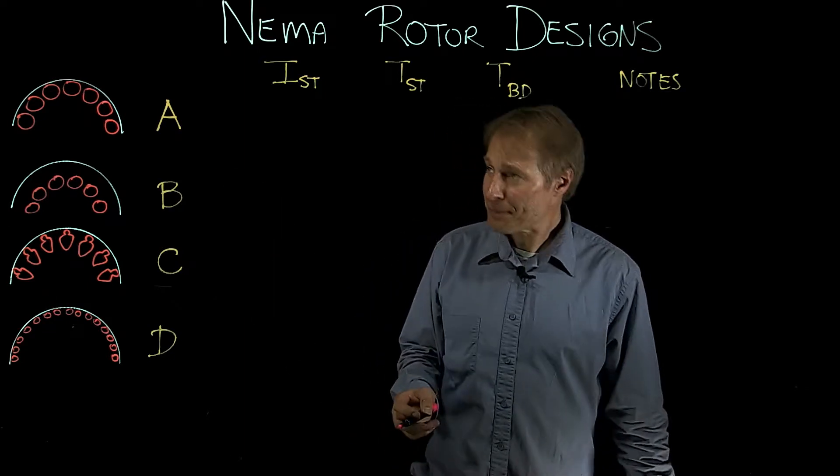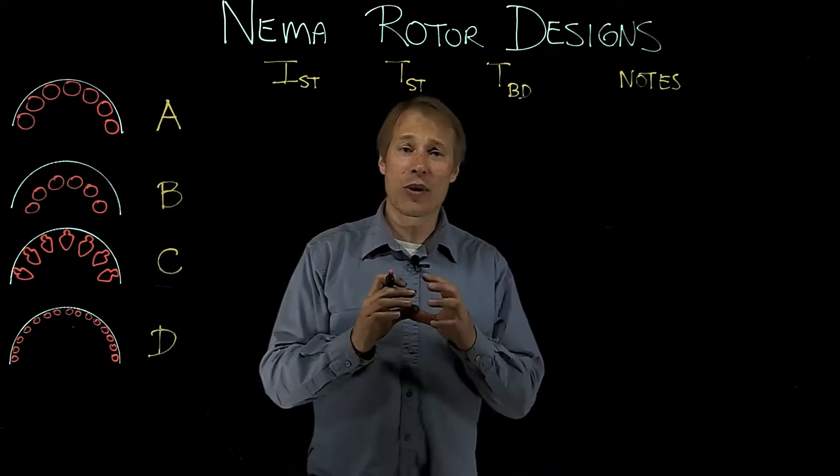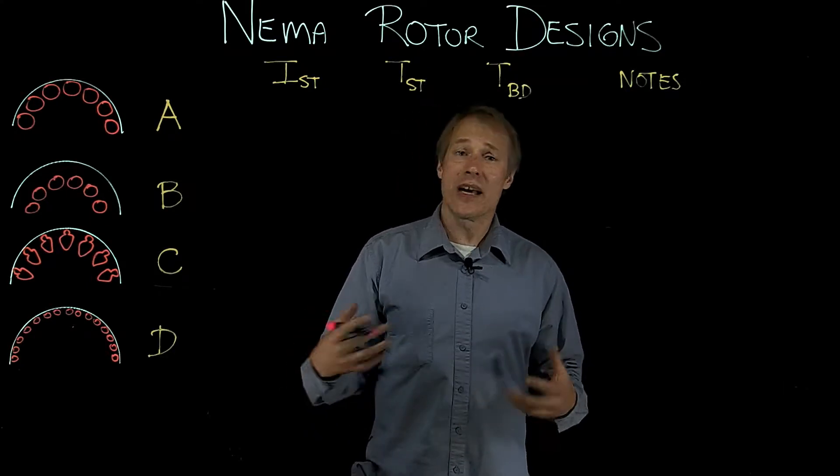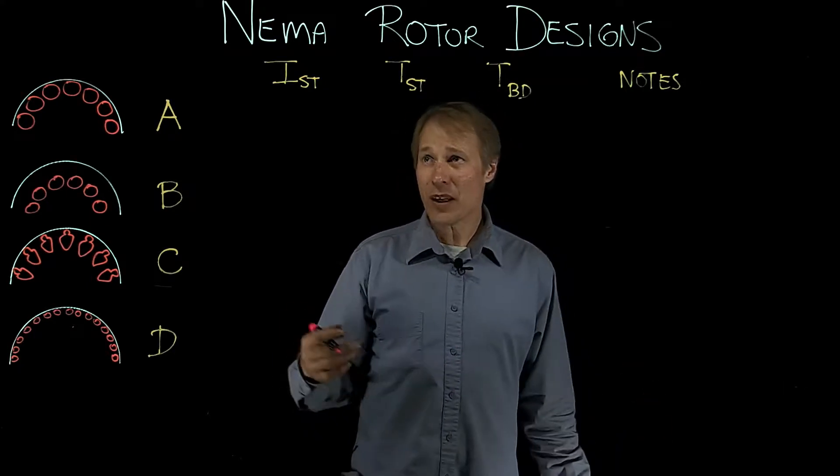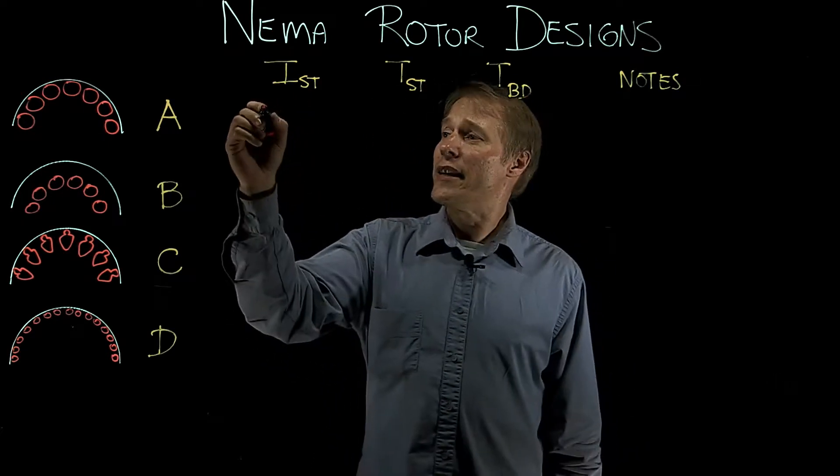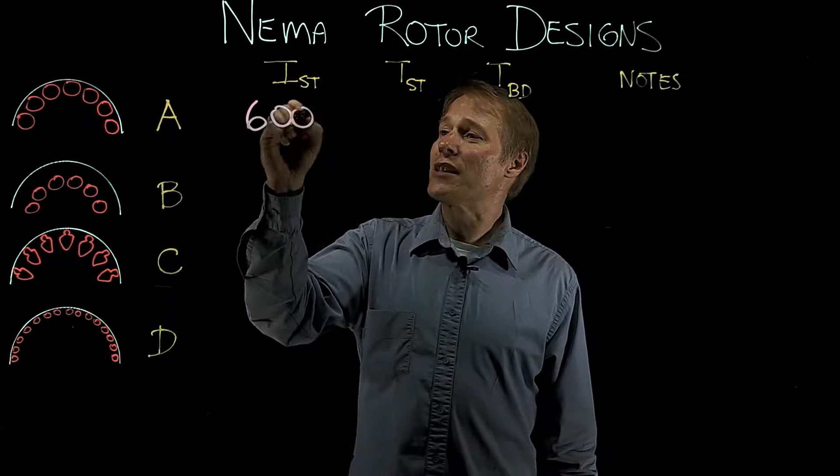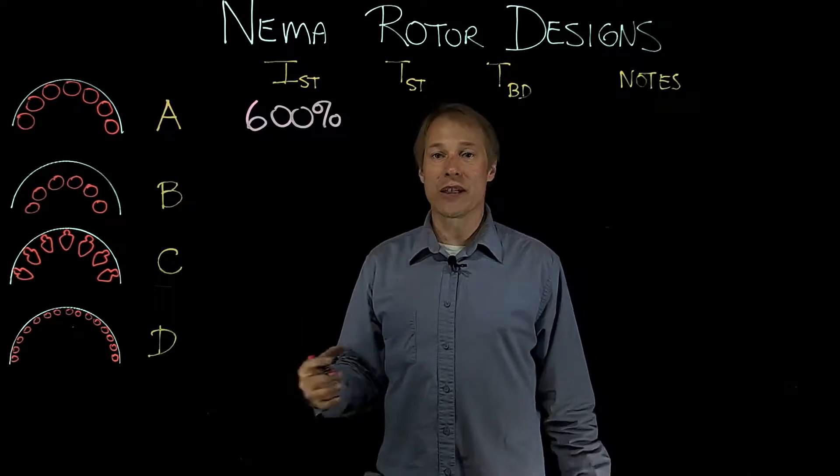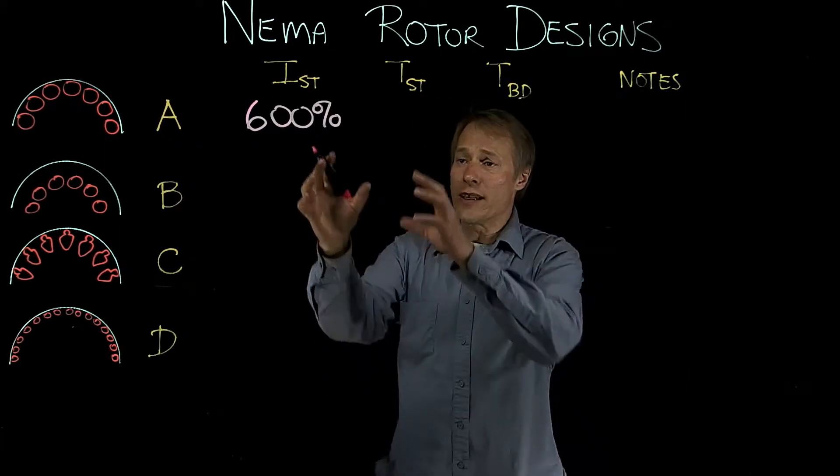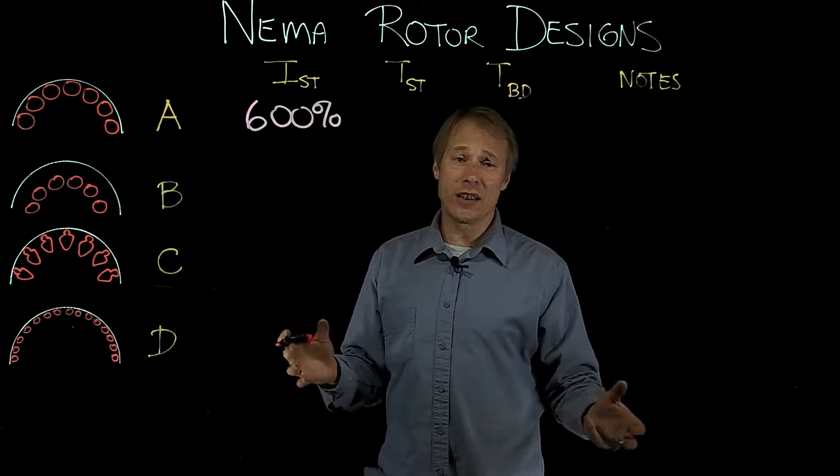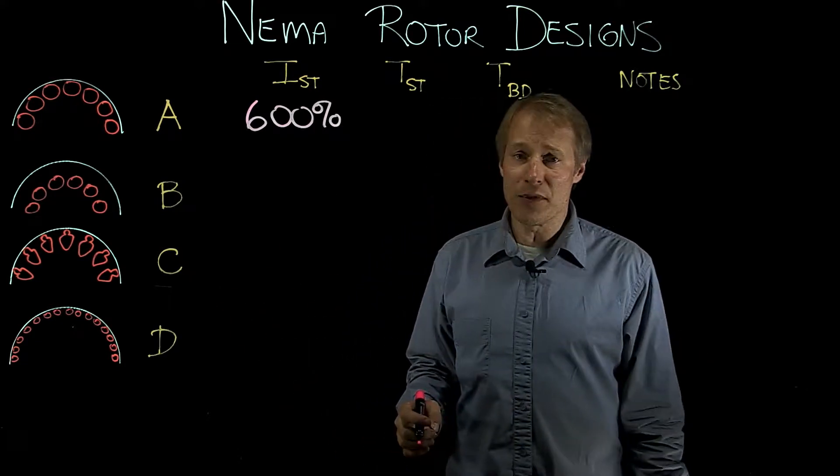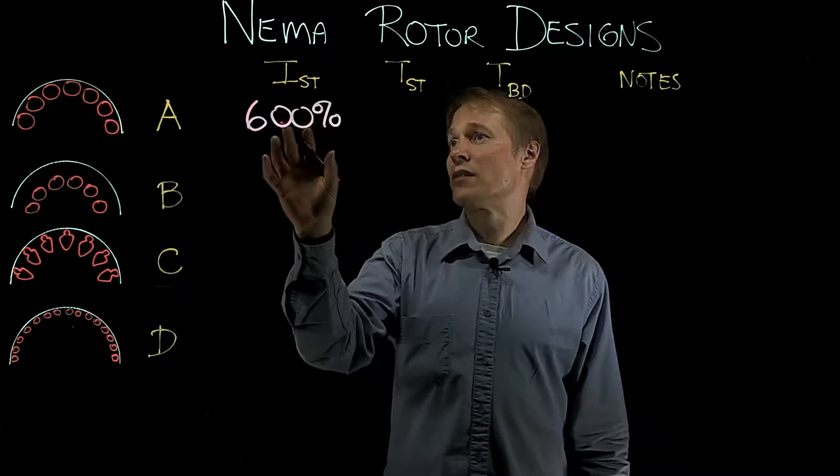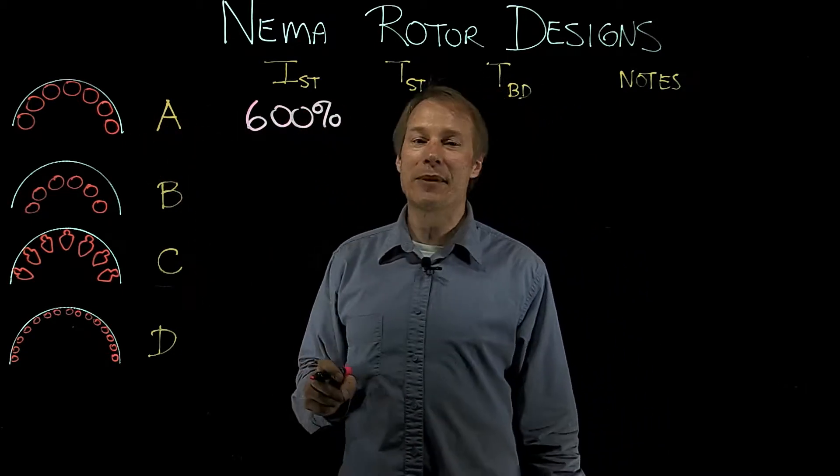So the NEMA A, as you can see the rotor bars are quite large, which means there's going to be a low resistance. If you have low resistance, you're going to have a high current, and the high starting current is going to be around 600% of the FLA of this motor. So that's the full load current. We're looking at percentages of all of these because that's going to change depending upon each individual motor. So 600% starting current for the NEMA A rotor.